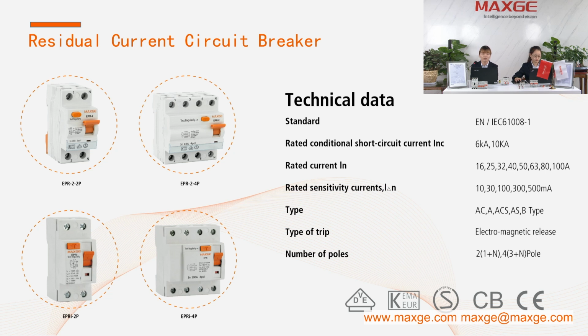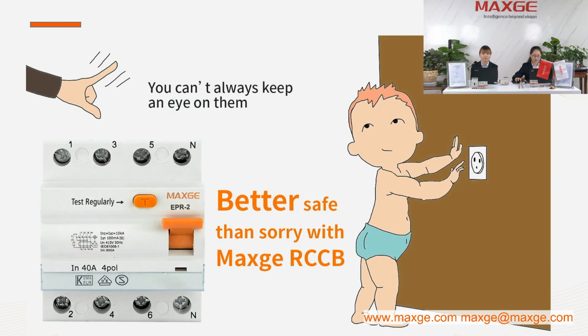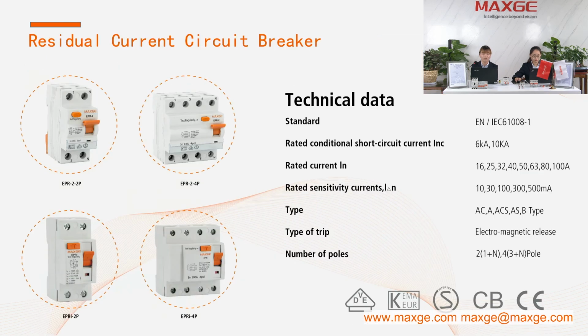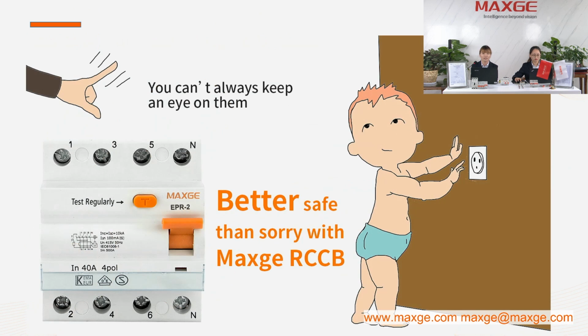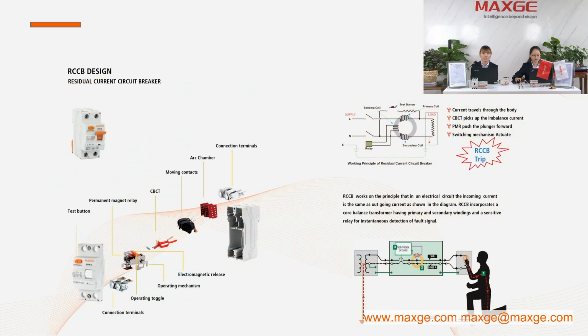Now let me introduce our RCCB internal part. From this graph, you will see the working principle of RCCB. When the current travels through the body, the transformer picks up the imbalance current, then the magnetic relay pushes the plug forward, then the switching mechanism acts.